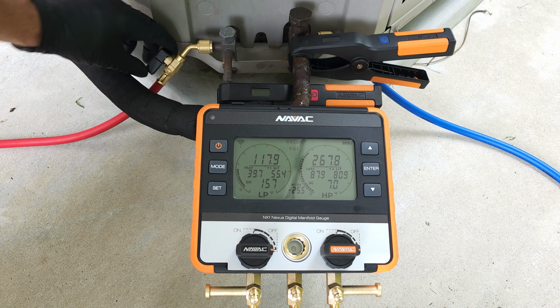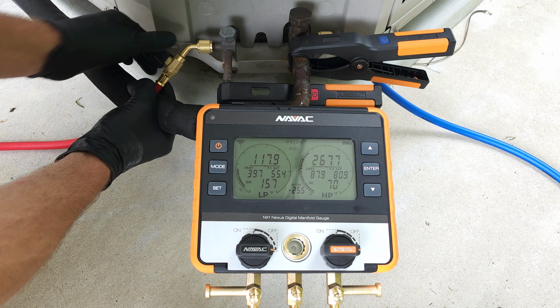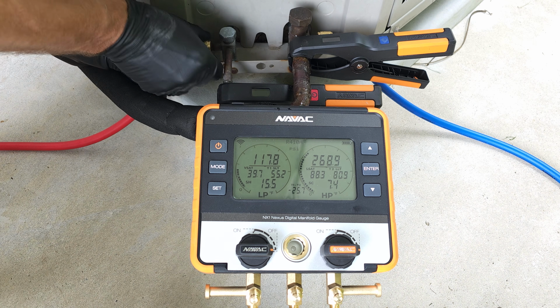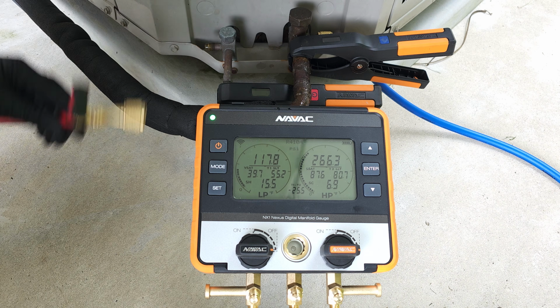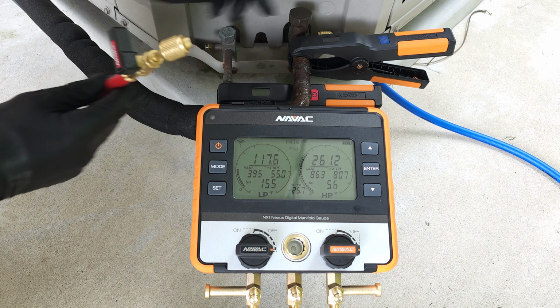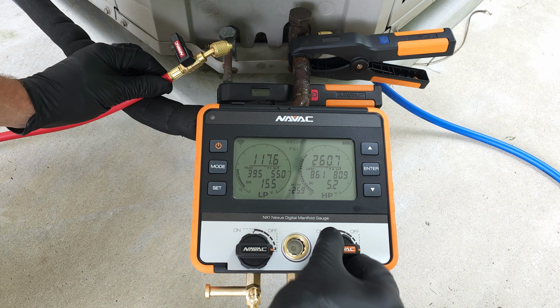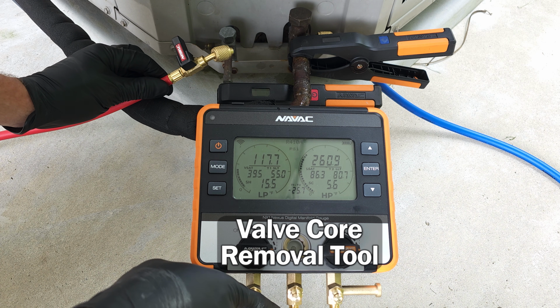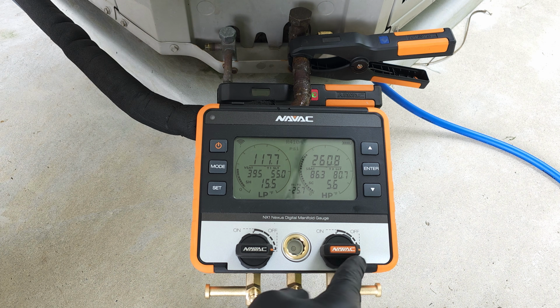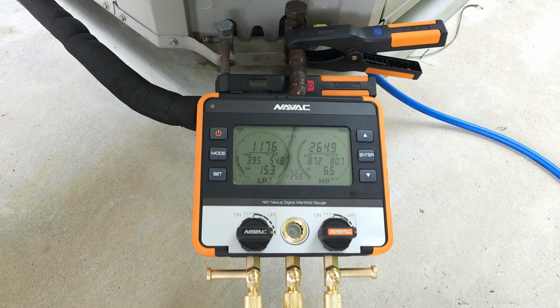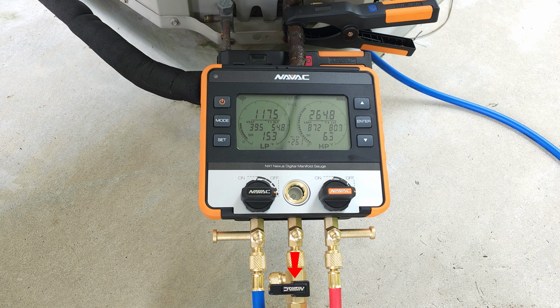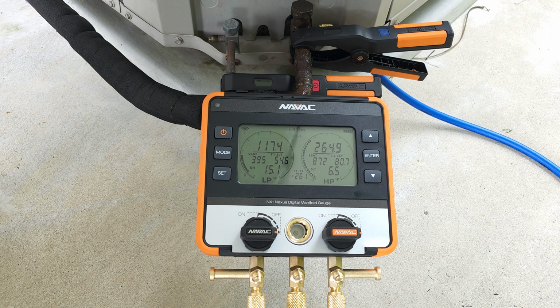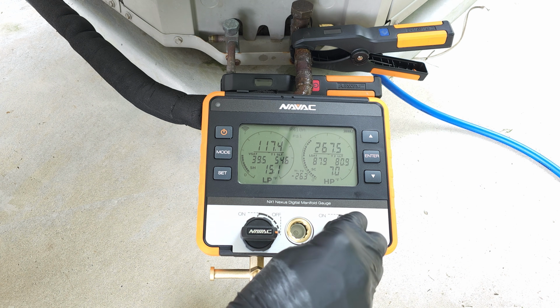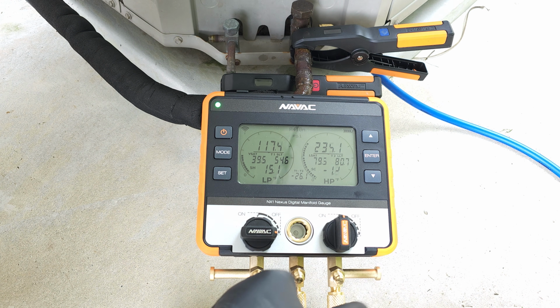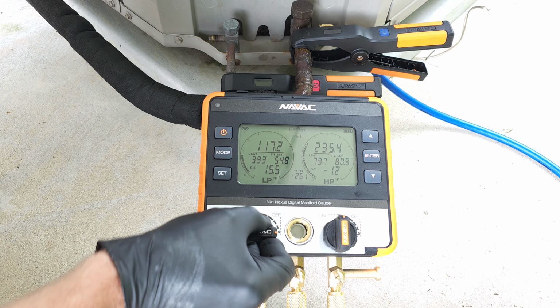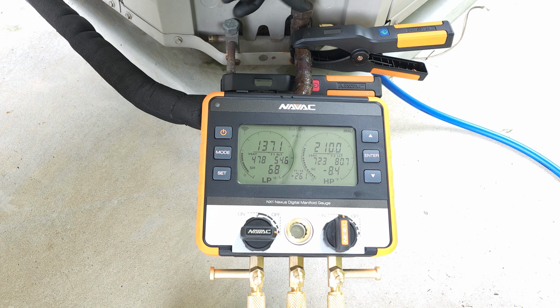Let's go ahead and disconnect our manifold from this system. So in order to do that, we're just going to shut this valve right here, unscrew this, and basically we're going to be charging the liquid that's in this hose back into the vapor side. And so we're going to do that a little bit at a time. So since we have this valve down here on the middle part in the closed position, we're just going to go ahead and open up our liquid side. So you can see that that valve right there is in the closed position, so we're safe right there. Let's go ahead and basically put this liquid right over into the side, and then we can charge a little bit at a time into the low side of the system. We don't want to steal refrigerant from this unit.